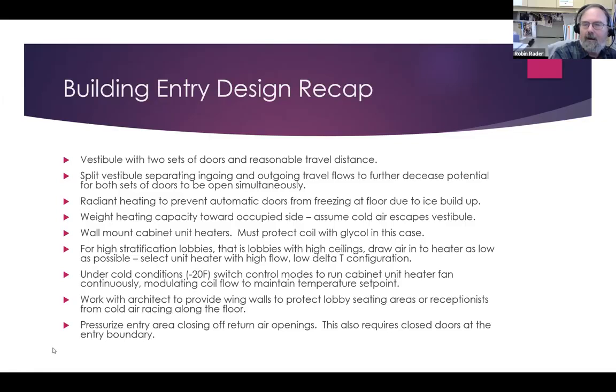Work with the architect to provide wing walls to protect lobby seating areas or receptionists from cold air racing along the floor. One thing that we did at the Rabinowitz Courthouse is we closed off all the return air openings out of the entry, this 2-story entry area, during cold weather operation. This was done a couple years after the building was occupied. It was the final thing that we did for this entry, and it helped significantly. So we pressurized the whole entry area and made a huge difference.